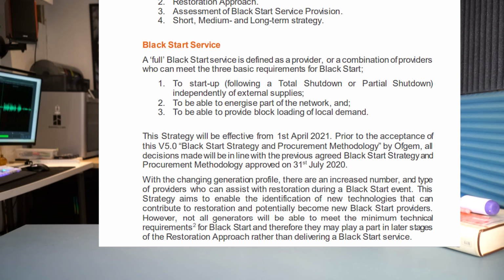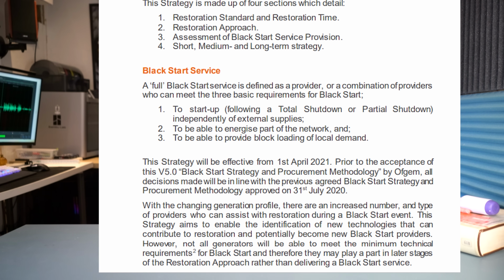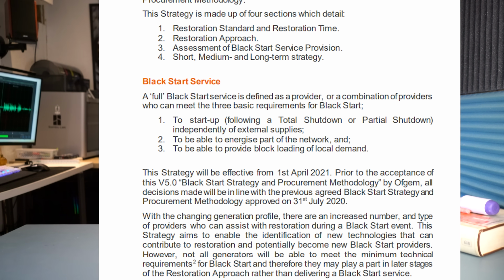Well, if we look at the top requirement of Black Start providers, we have a very specific point on Black Starting the grid. The provider must be able to cold start with no grid connection in order to be relied upon as a Black Start provider, so nuclear is out of the question, because it takes a load of power and ramp up time to get going.